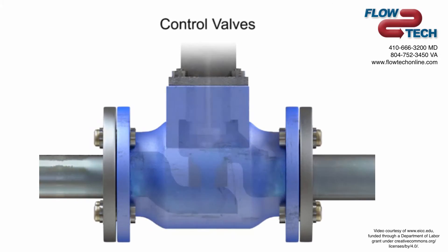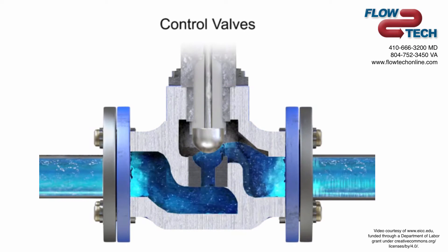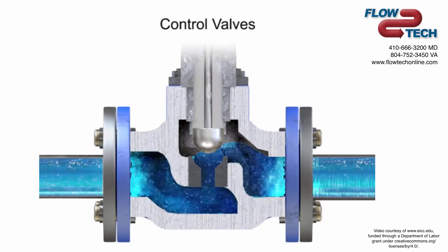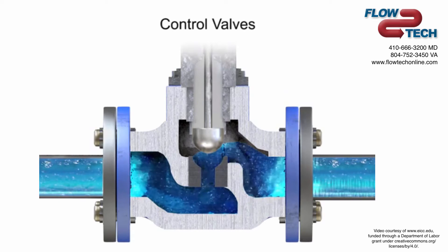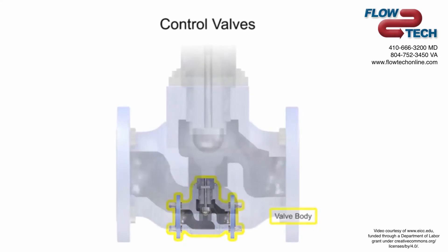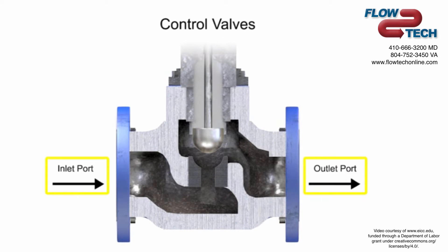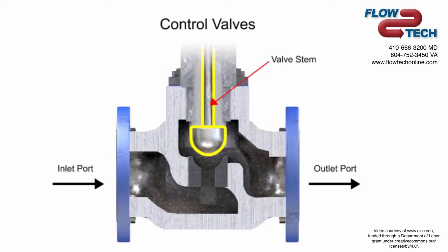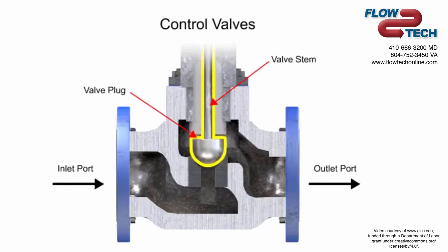Control valve actuators control fluid in a pipe by varying the orifice size through which the fluid flows. Control valves contain two major components: the valve body and the valve actuator. The valve body provides the fluid connections and a movable restrictor comprised of a valve stem and plug that is in contact with the fluid to vary the flow. The valve actuator is the component that physically moves the restrictor to vary the fluid flow.